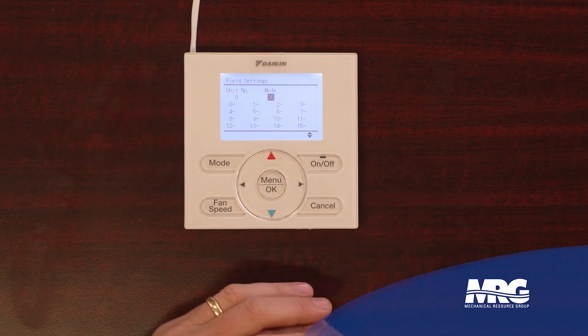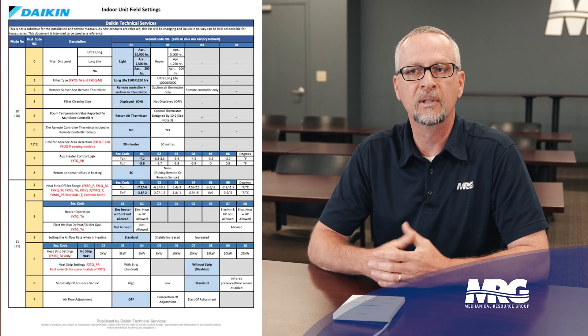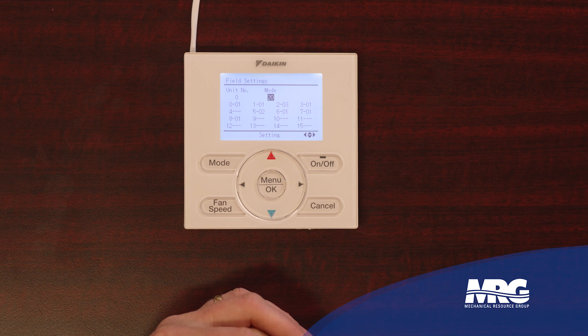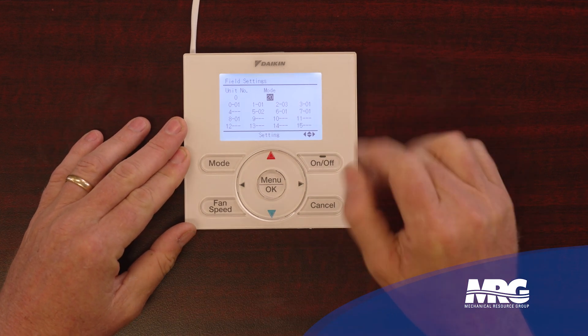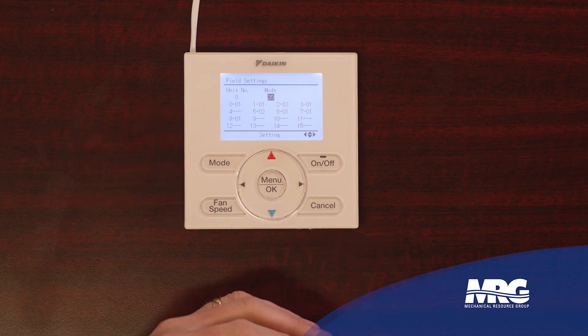I'm going to enter field settings. Now I get a lot of numbers and it can be very confusing if you've never used this device before, especially if you don't have the field settings table — and you'll see that popping up on the side screen here. The first thing I want to talk about is where you see on the top where it says unit number and mode. I may have multiple indoor units connected to this one stat. That's when I would want to scroll through and determine which indoor unit I want to make a change to. In the demonstration we're doing here, I just have a one-to-one — this stat is on one cassette unit. Remember that you can have up to 16 indoor units controlling off of one NAVSTAT, and if I wanted to make individual changes to one of those indoor units, that's where I'd need to scroll down and select the correct unit.